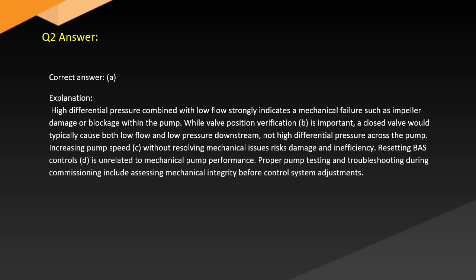Answer. Correct answer: A. Explanation. High differential pressure combined with low flow strongly indicates a mechanical failure such as impeller damage or blockage within the pump, while valve position verification (B) is important. A closed valve would typically cause both low flow and low pressure downstream, not high differential pressure across the pump.